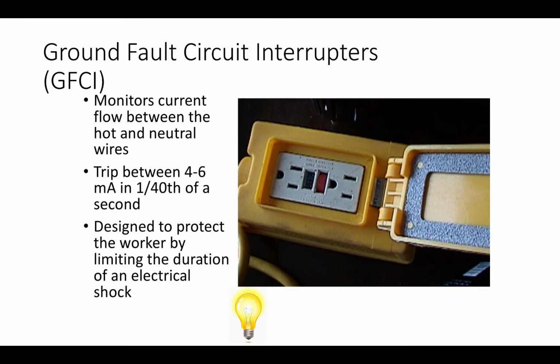Ground fault circuit interrupters monitor the flow between the hot and neutral wires. They will trip between 4 to 6 milliamps in 1/40th of a second. In other words, if there's a difference between the hot and neutral, which means some current is going someplace else, the GFCIs will trip in 1/40th of a second. They are designed to protect the worker by limiting the duration of an electrical shock.